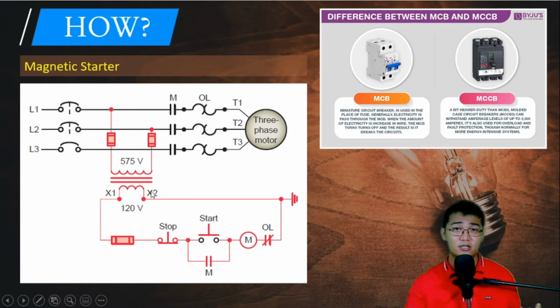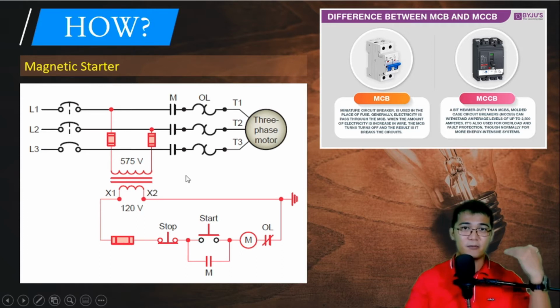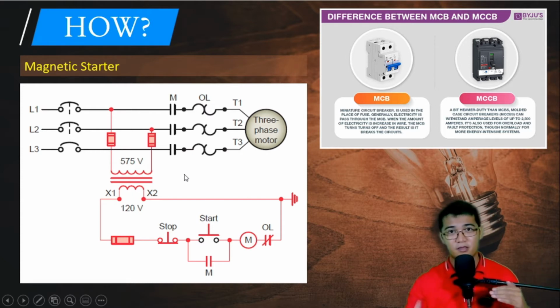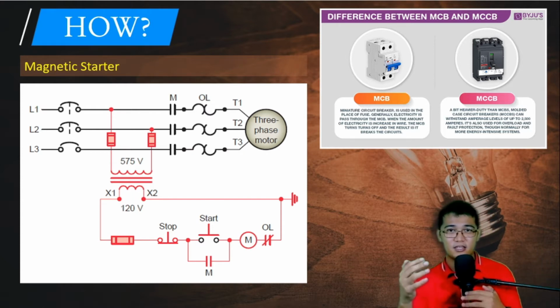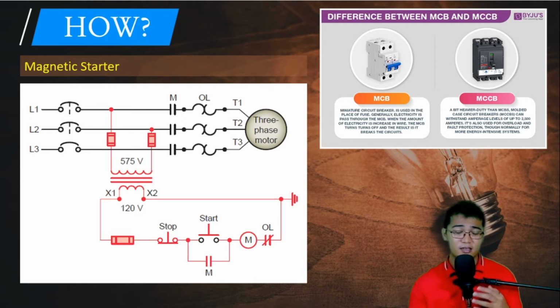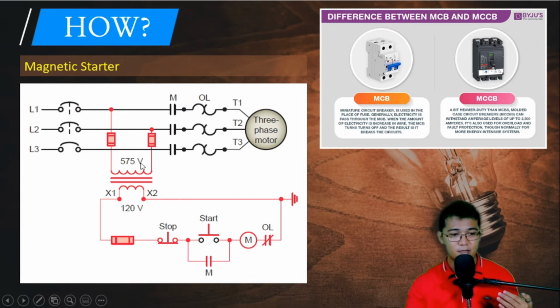We notice here we have this symbol, which is actually for a transformer. Basically, the function of a transformer is to step up or step down the voltage. In the case of this particular control circuit, from 575 on the primary side, it becomes 120 volts on the secondary side. So this is actually a step down transformer, from a 575 volt supply to 120 volts on our control circuit.